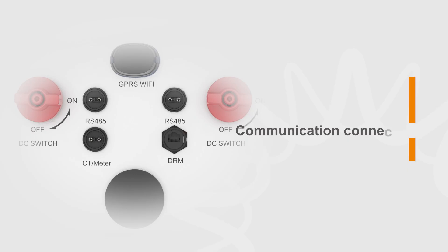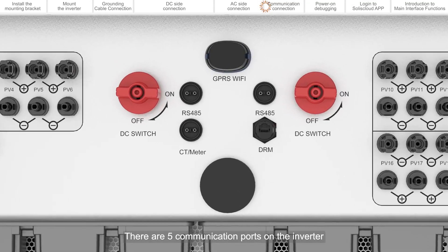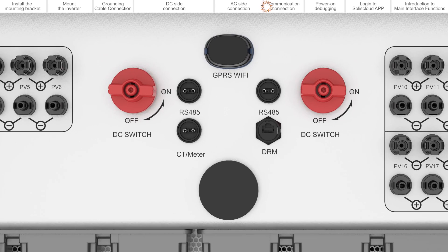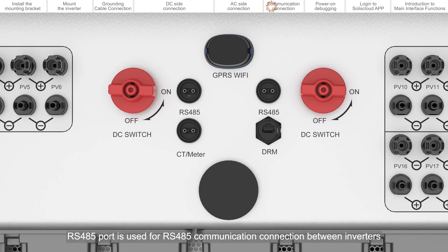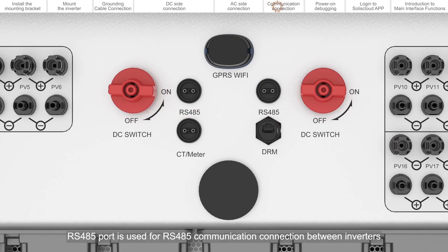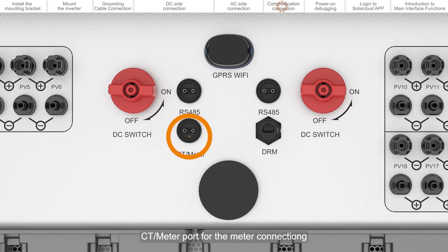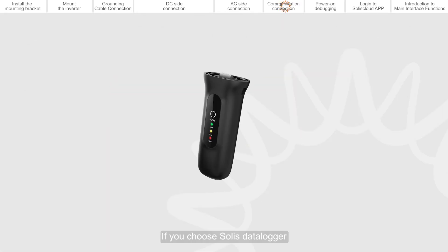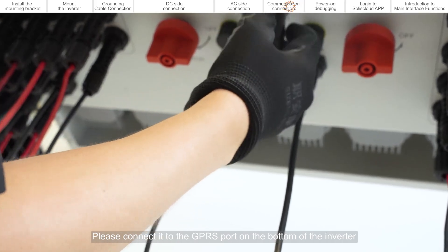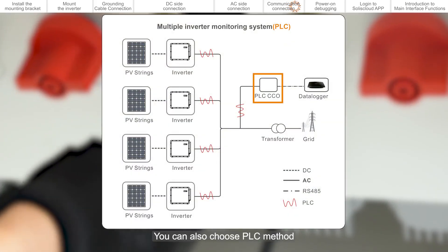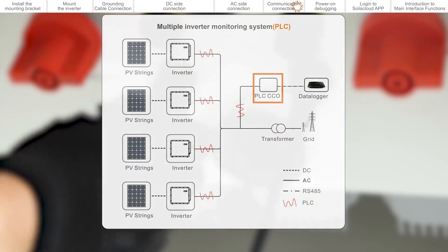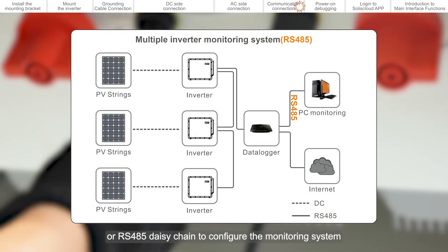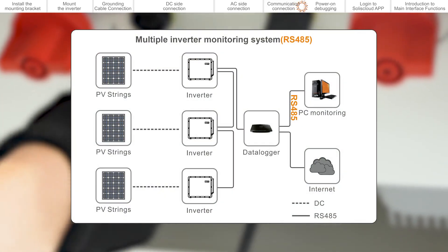Communication connection. There are five communication ports on the inverter. GPRS WiFi port is a dedicated port for monitoring sticks. RS485 port is used for RS485 communication connection between inverters. The DRM port is used for DRM connections. CT Meter port for the meter connection. If you choose SOLIS Data Logger, please connect it to the GPRS port on the bottom of the inverter. You can also choose PLC method or RS485 daisy chain to configure the monitoring system.